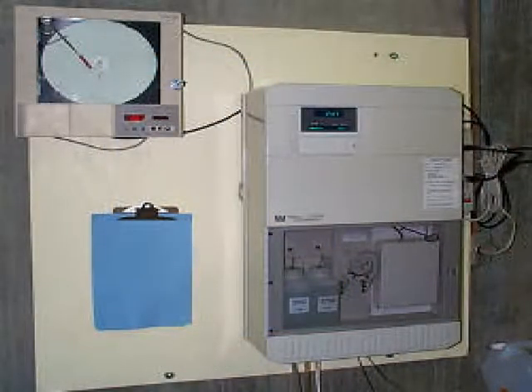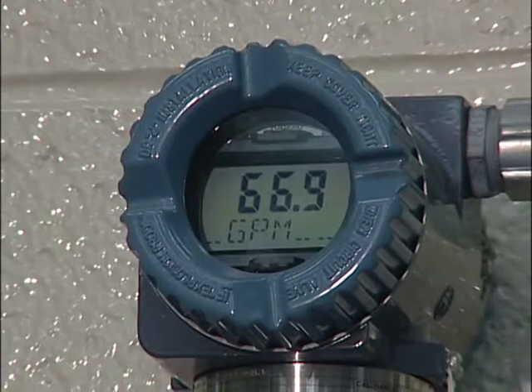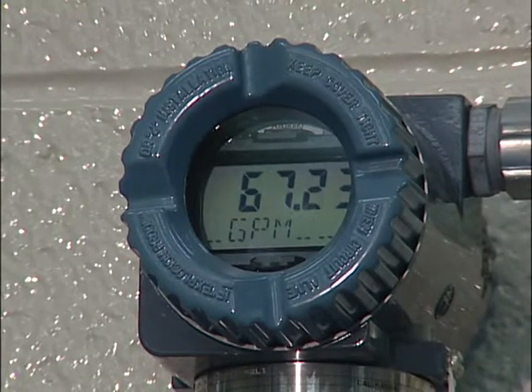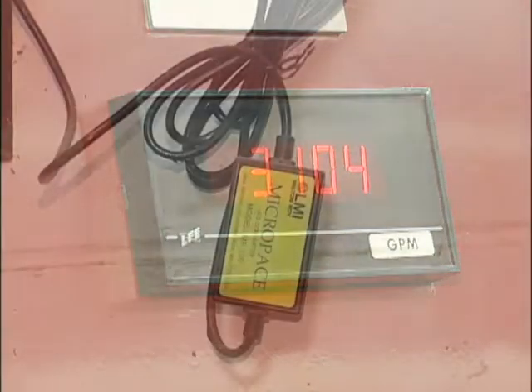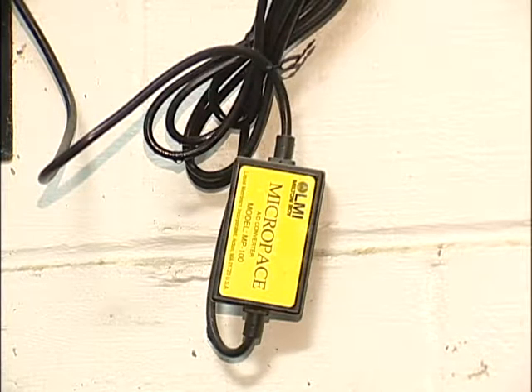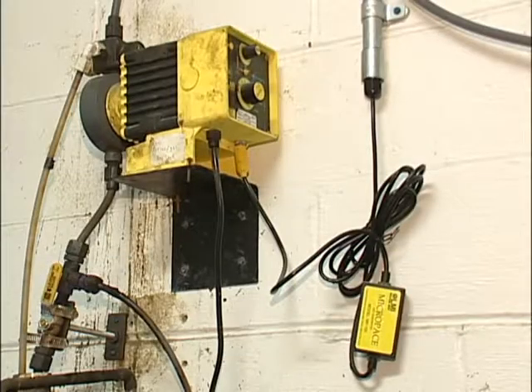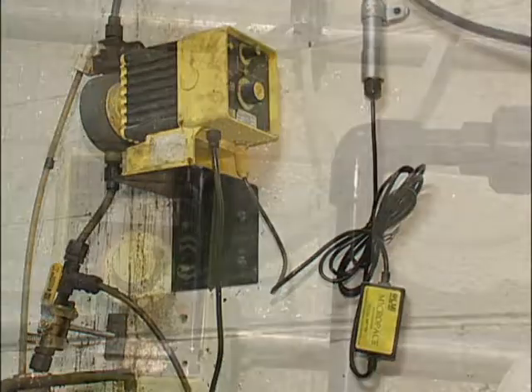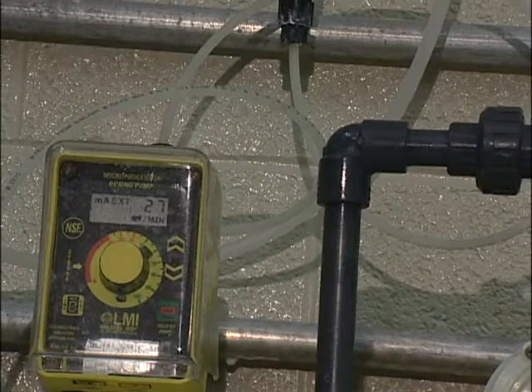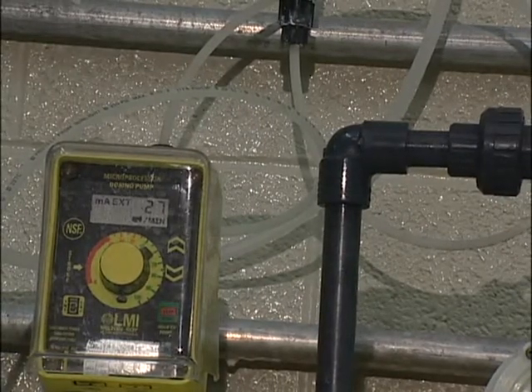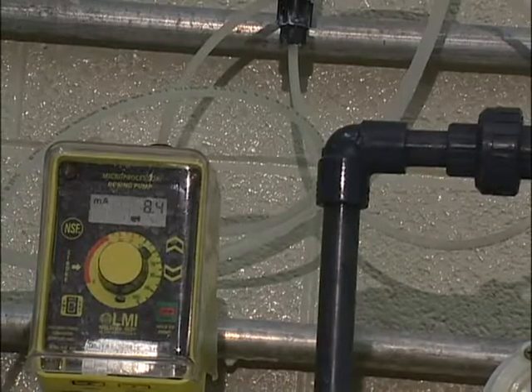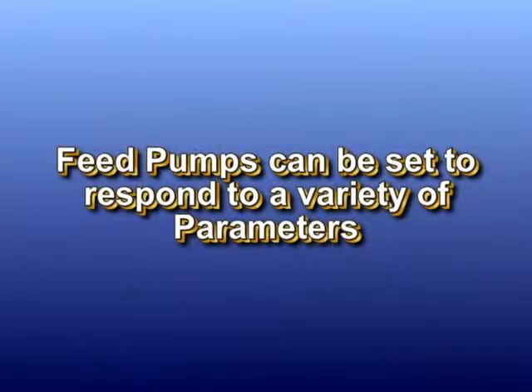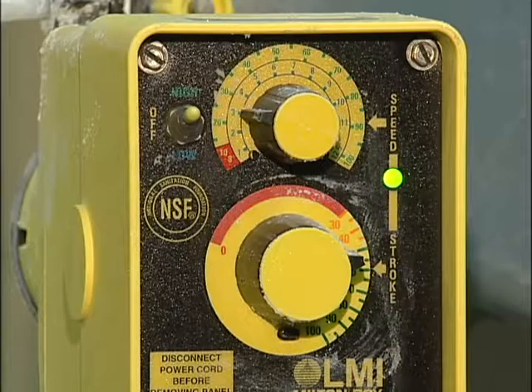Some pumps are set to pump a fixed amount whenever they are in operation; others can be set to respond to varying input signals to yield differing amounts in response to changing conditions. For example, pumps can be flow-paced so they vary delivery rates with changing flow rates. A sensing unit picks up the rate of flow and sends a corresponding signal to the chemical feed pump, delivering more chemical for higher flows and less for lower flow conditions.